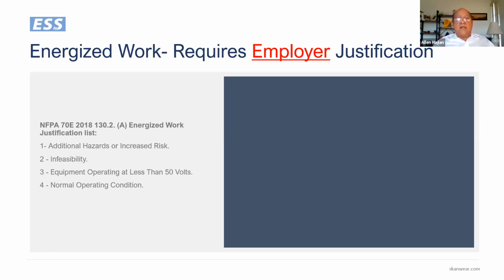One of the most important things to remember is that energized work requires justification. Most employers leave it up to the local electrician to decide whether this work is going to be done energized or not. And that's not the right thing to do. We need to make sure our employers are engaged in why we're doing energized work, how we're doing energized work, and what our justification is. It's something that the employer has to stand behind.